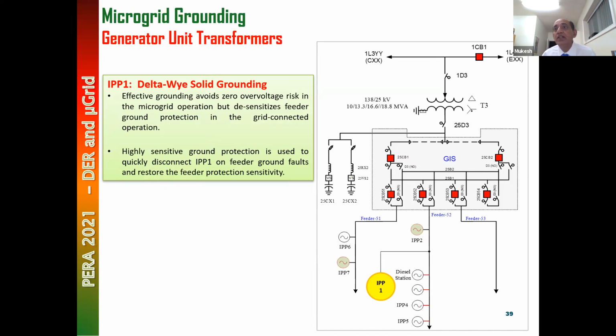Grounding is very important because we are going to operate this IPP as a microgrid. This one was solid grounded, delta-Y solid grounded. Now you should ask me a question. This is the largest generator on a weak system. If we do solid grounding here, we are going to have desensitization of ground fault. Yes, we are going to have it. But how do we overcome that? We put in a very sensitive ground protection here.